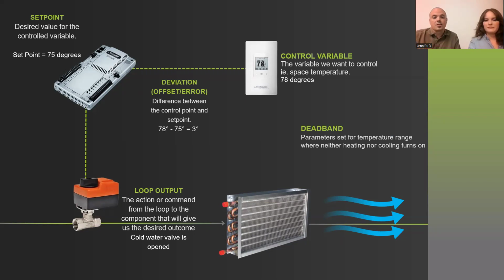What that means in this scenario is we're going to wait until the temperature gets all the way up to, say, 76.1 degrees. We've exceeded the deadband. Now the loop can actuate the output to start bringing the temperature down within tolerance. And it's probably going to continue to do that. This is especially true in things like a compressor where we're staging it on and off. We're going to keep that output running until we bring it a little bit past the set point.